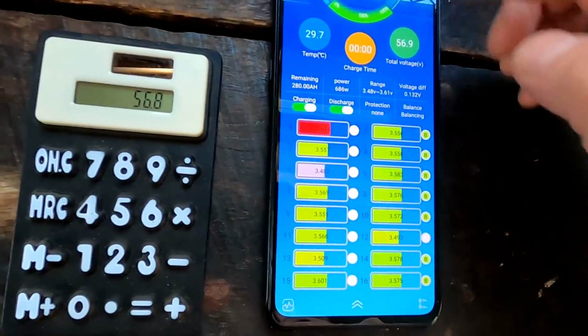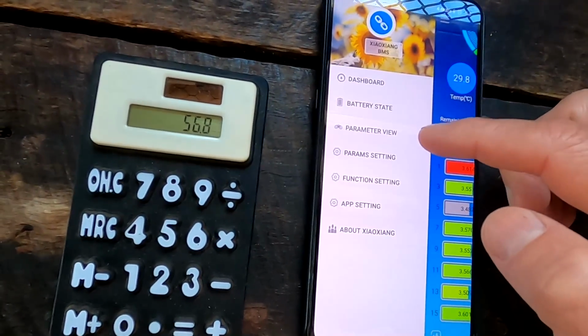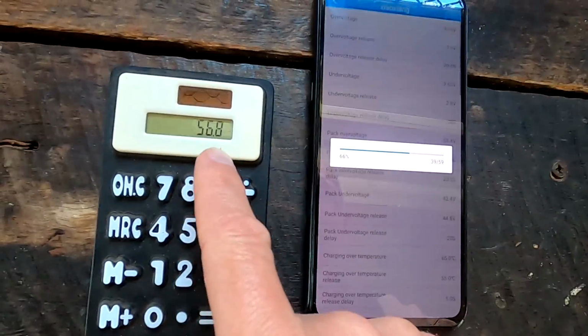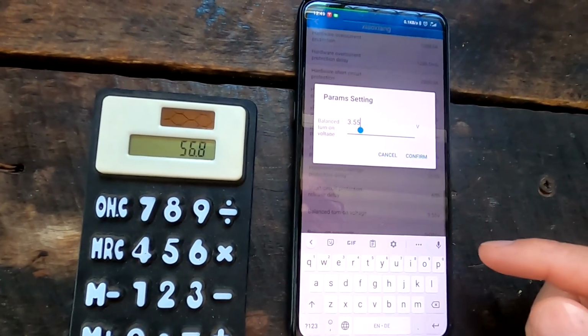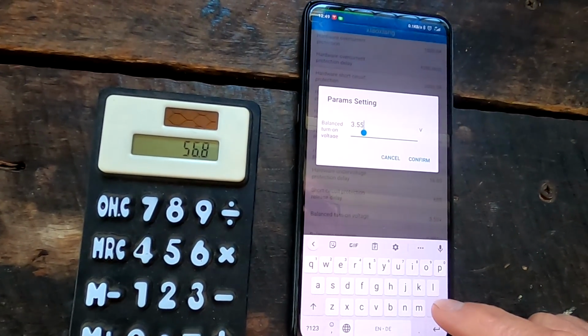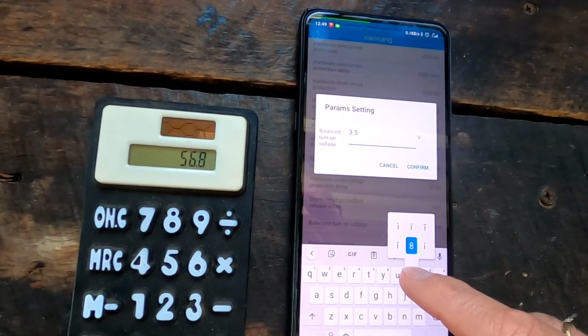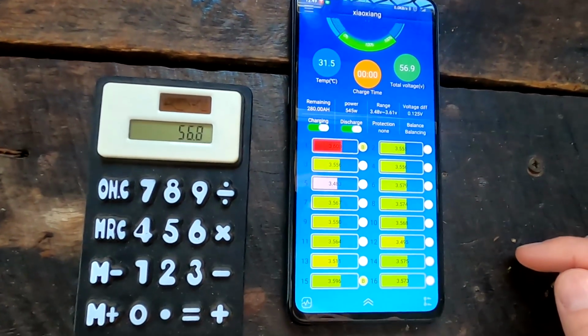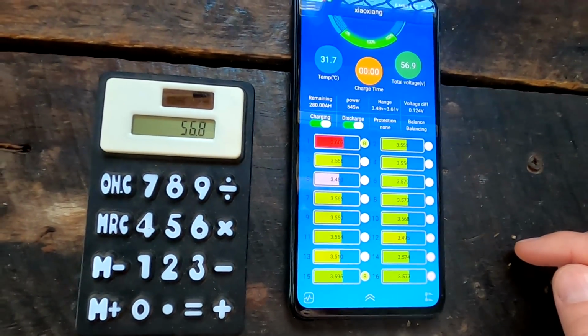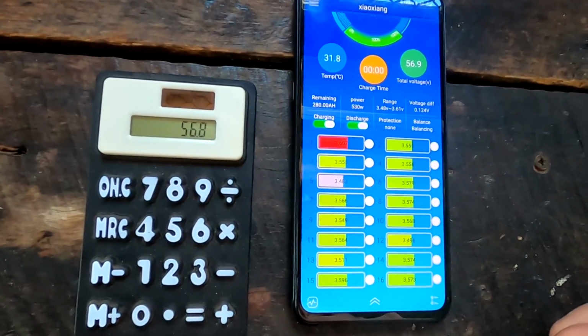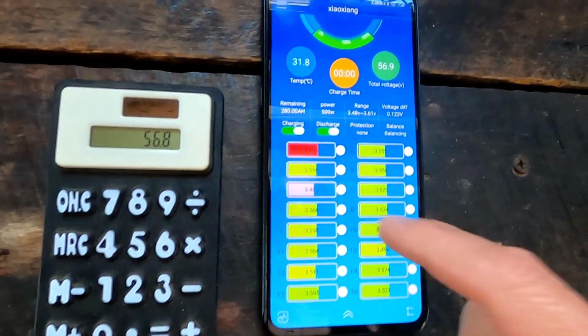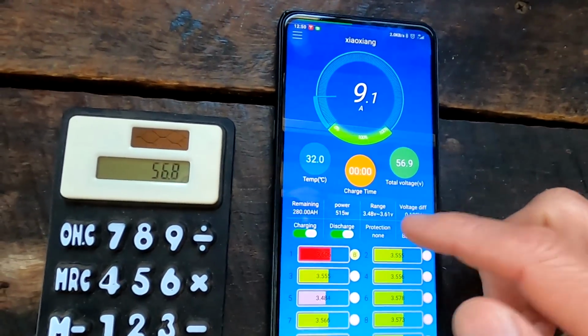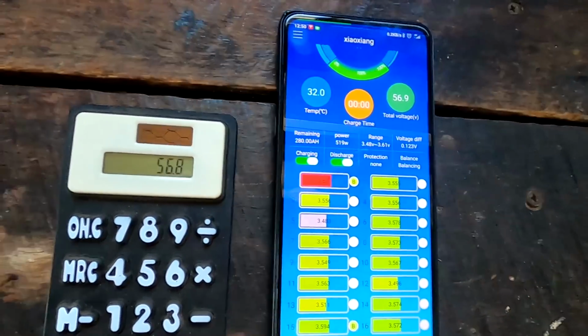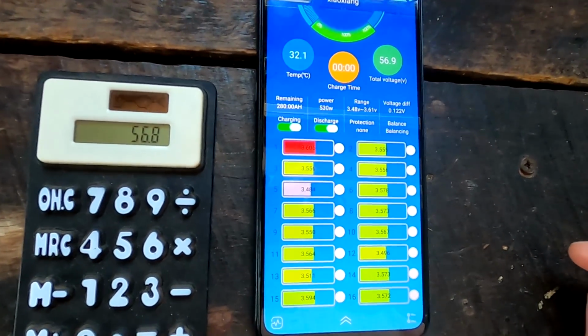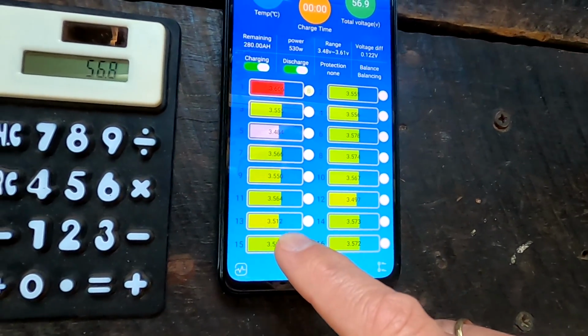Now you can see they're all balancing because we needed to change the settings here as well. This is 3.55, our absorption voltage per cell, and we need to go a bit higher, so probably to 3.58 - everything above that will be balanced now. See, we have 3.6, still charging with 10 amps. So they should all reach 3.55 at some stage.